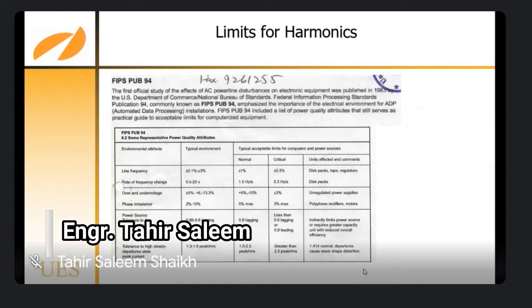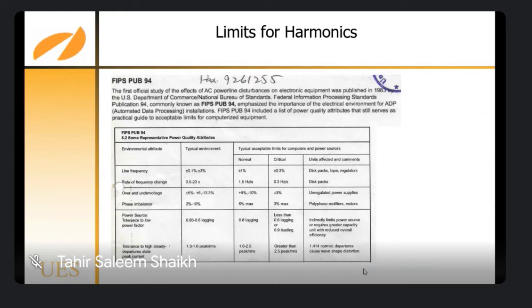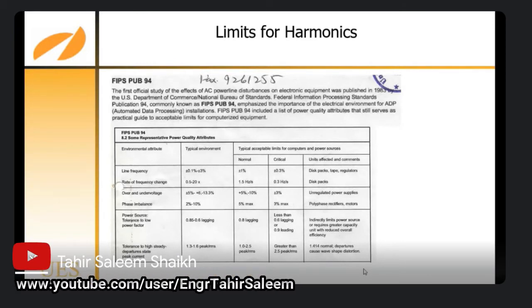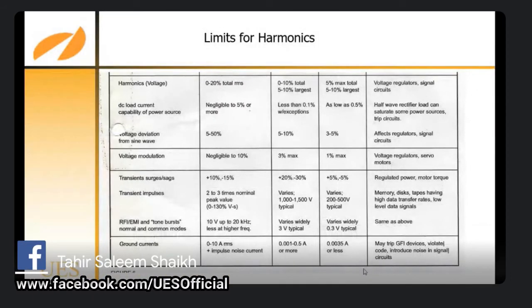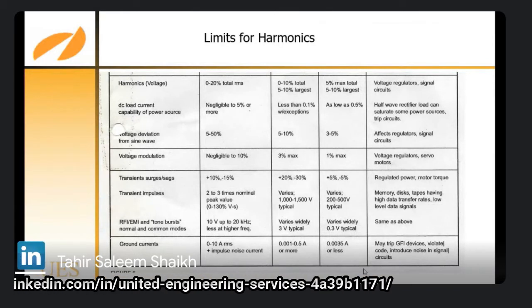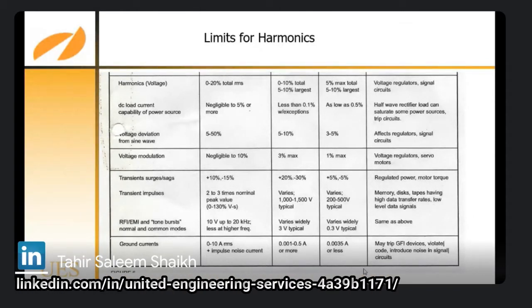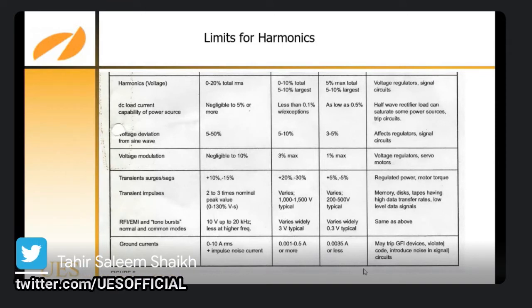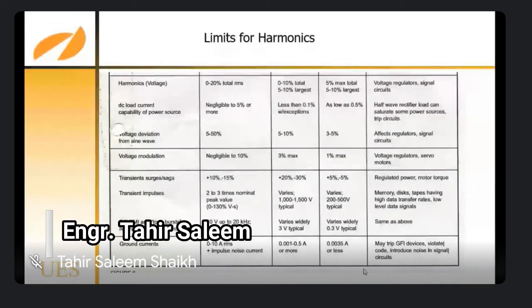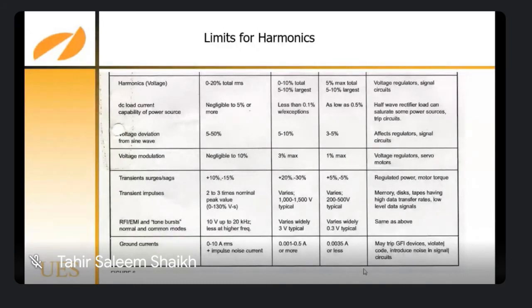Power source tolerance to low power factor 0.85 to 0.6, 0.8 lagging. Tolerance for high repetitive peak currents 1.3 to 1.6 is the normal environment. Typical environment 1 to 2.5% peak time and greater than 2.5 to peak time. Now harmonic voltage will be normal with 0 to 20%, but for the critical load, the normal load is 0 to 10% and 5% maximum total for the critical load. DC load current capability of power source negligible to 5%, less than 0.1%. Voltage deviation from the wave 5 to 50%, 5 to 10%, and 3 to 5%.